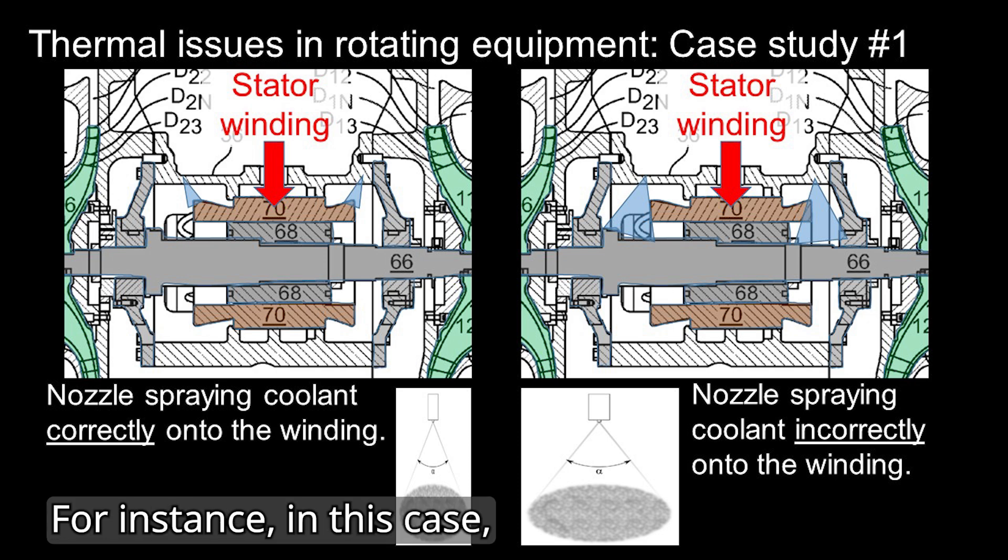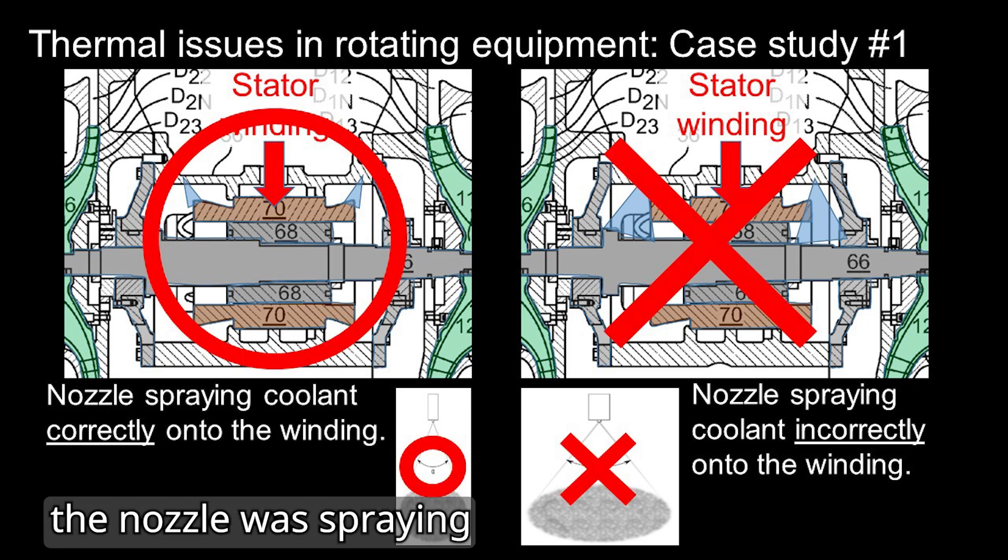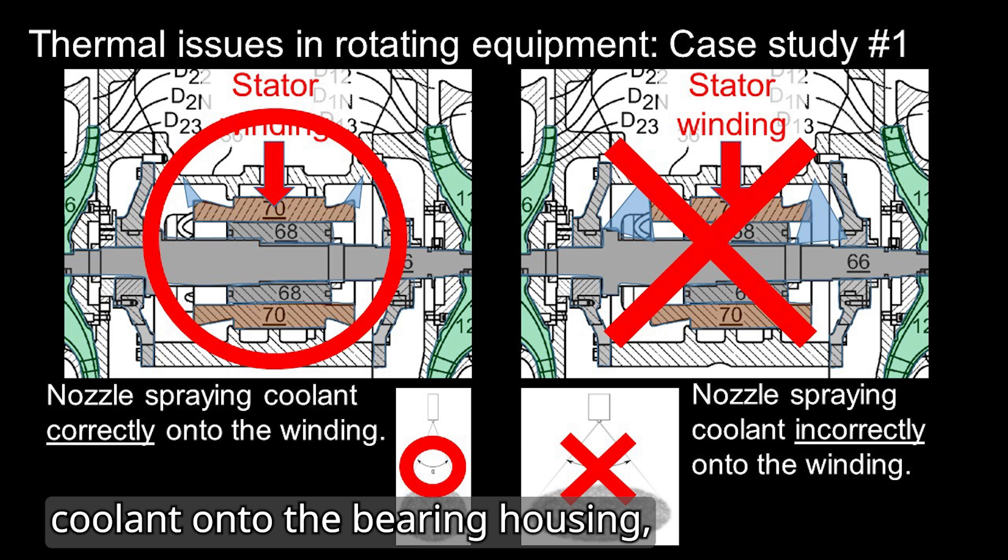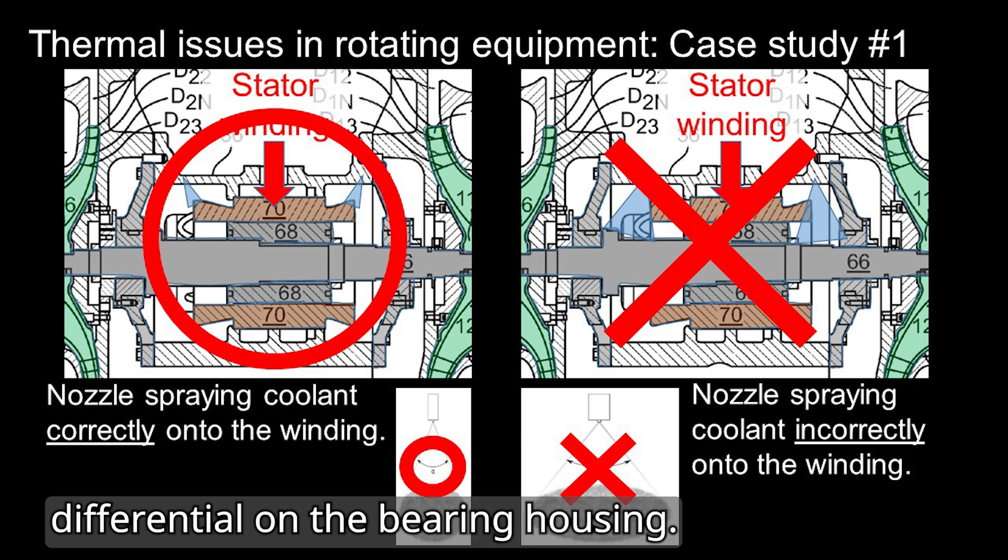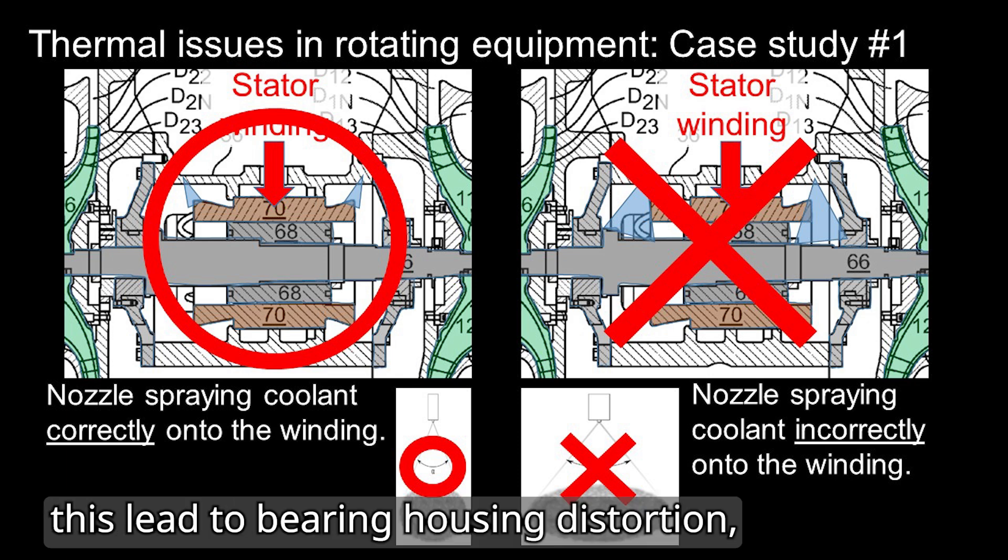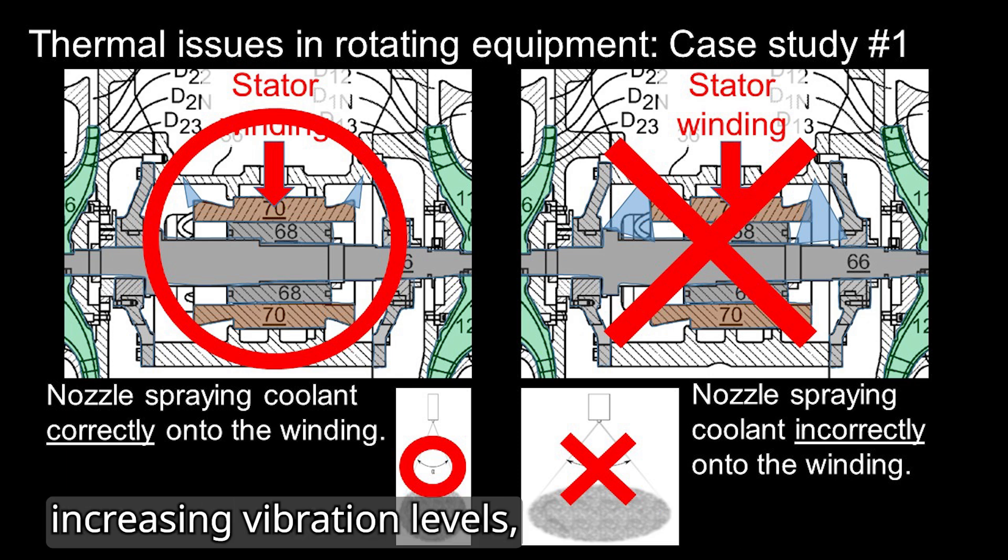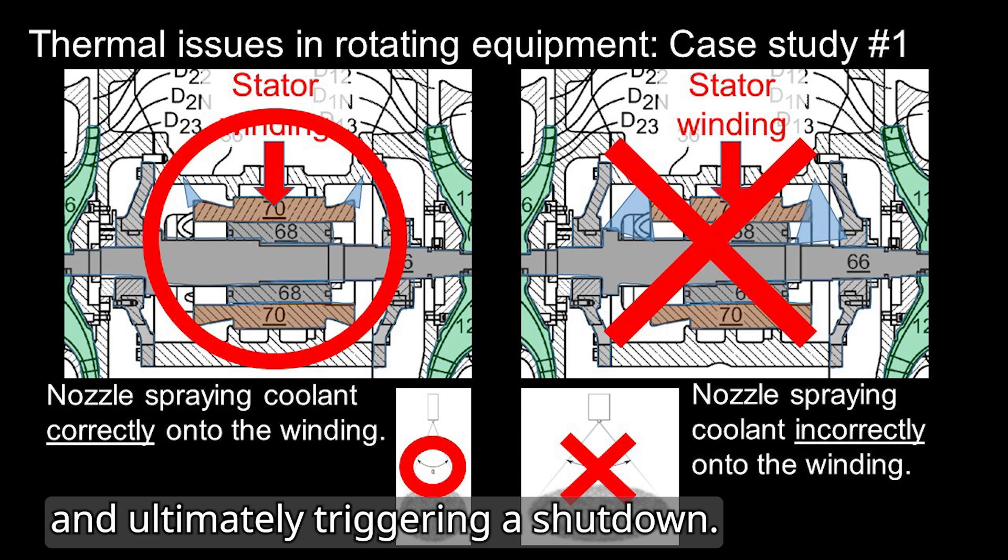For instance, in this case, the nozzle was spraying coolant onto the bearing housing, causing temperature differential on the bearing housing. Over time, this led to bearing housing distortion, increasing vibration levels, and ultimately triggering a shutdown.